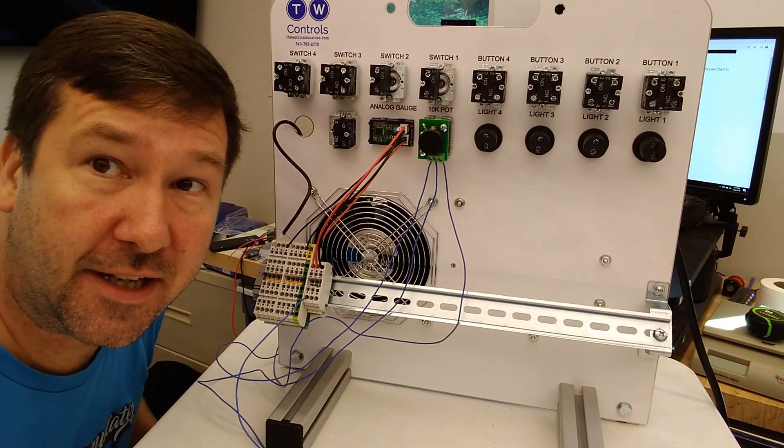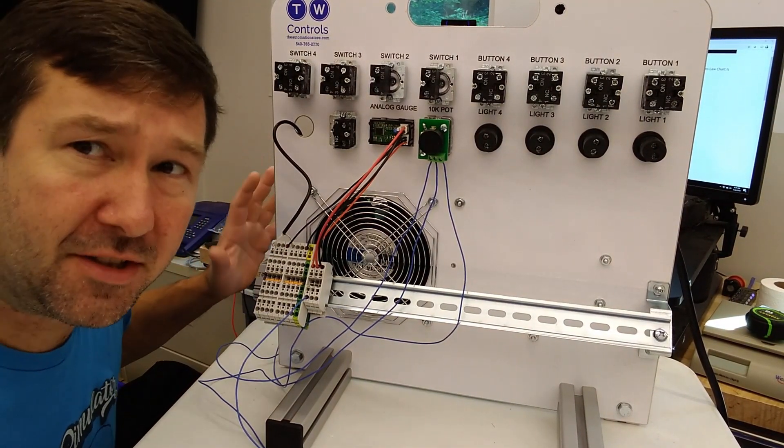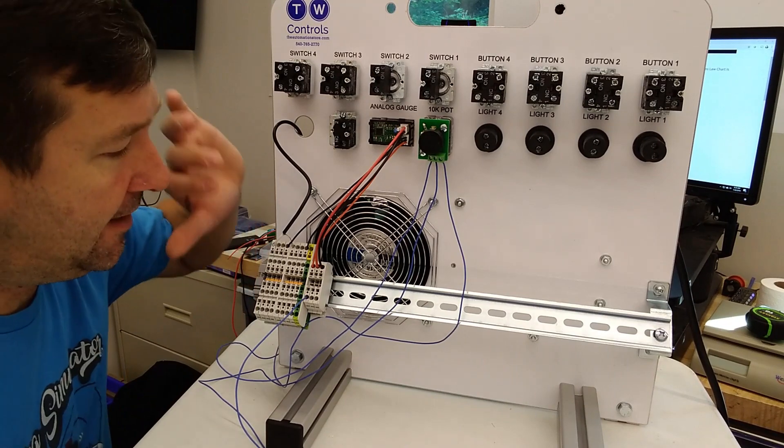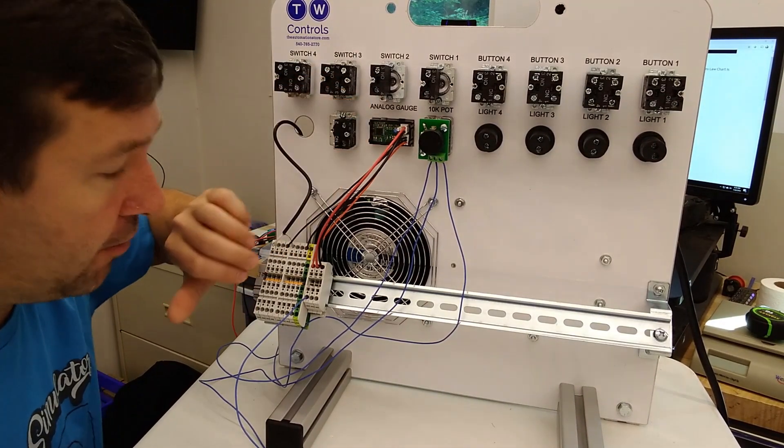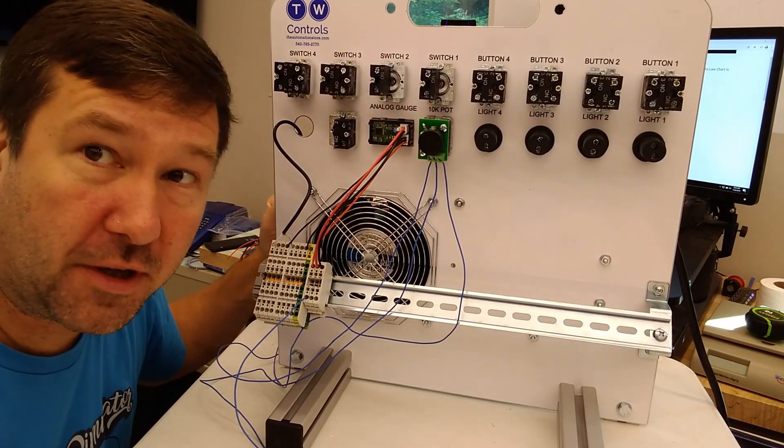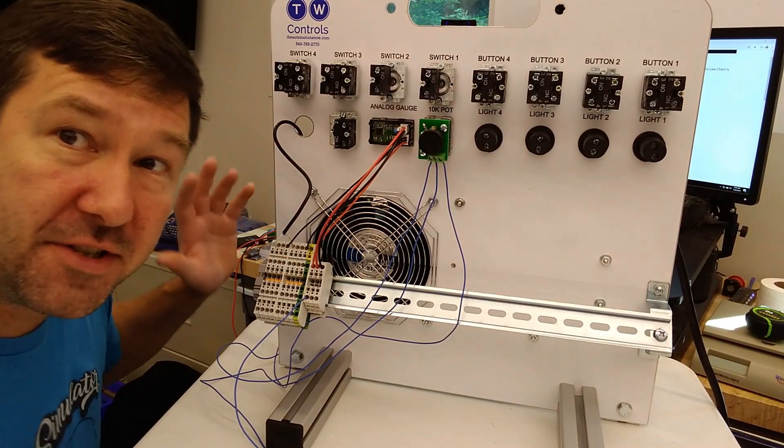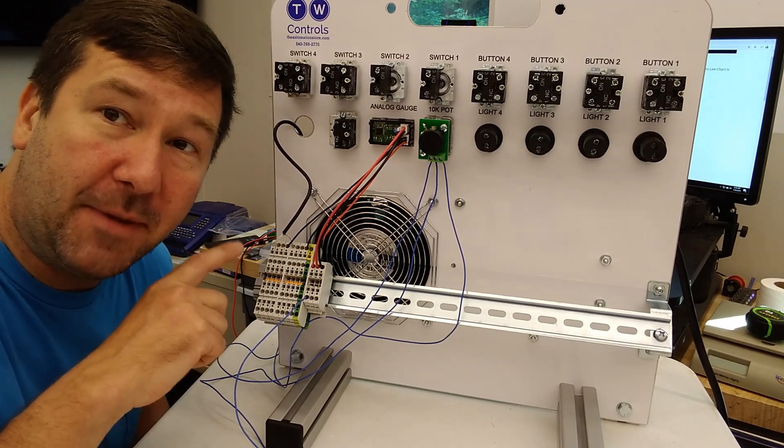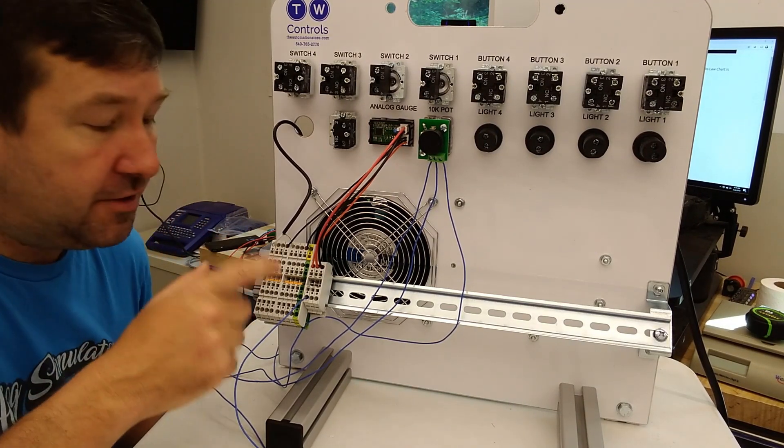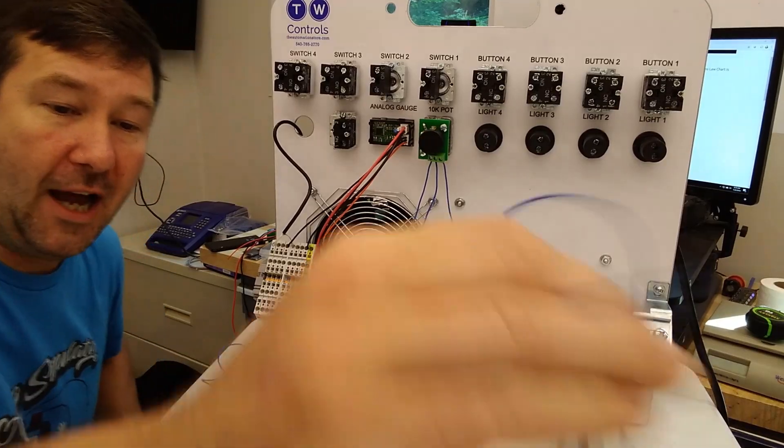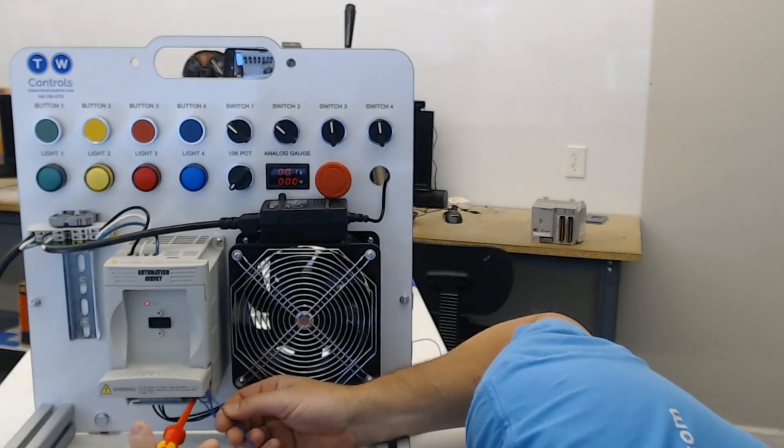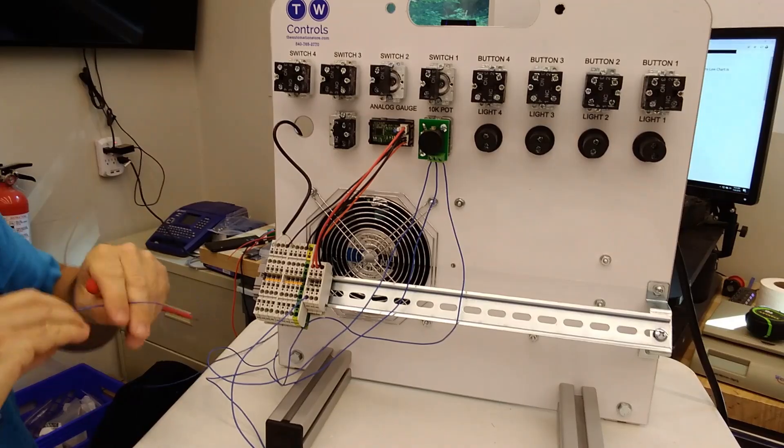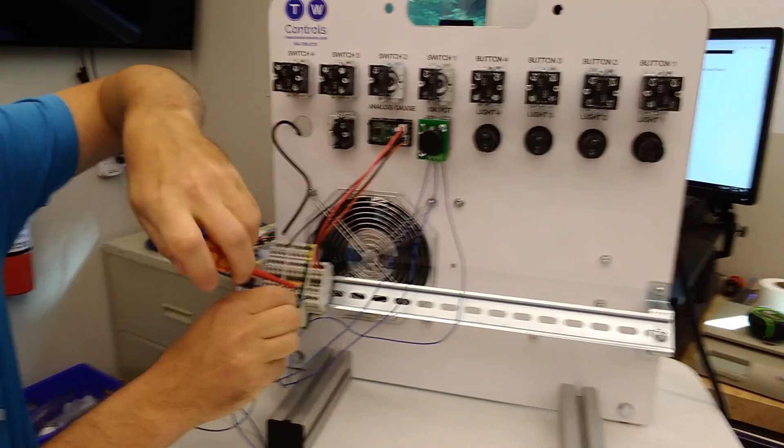Now there's one additional connection that will need to be made for our trainer and also for a lot of setups, and that is our analog display is powered off the 24 volt of our trainer, but the 10 volt we're getting is off of our drive. So they are separate power supplies. So we'll need to tie the common of the drive 10 volt to the common of our 24 volt power supply. So I'm just going to add a second wire right beside this analog common and connect it to our 24 volt DC common.